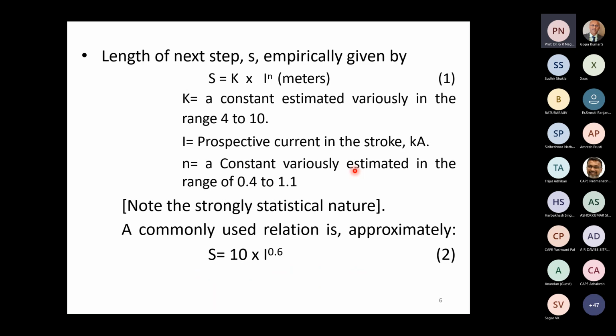Now, supposing the leader has come to the point P naught as shown in the previous figure, the length of the next step was shown to be related to the prospective current I in the stroke by the relationship given here. Yes, the next step distance is equal to a constant K multiplied by the current I raised to the power of N. Now, remember, lightning has many statistical parameters. That means we cannot have one constant for K. Similarly, we cannot have one constant for N. For strokes which have occurred in some area, for various currents in that region, we may find different values of K and N. Like that, the constant K, estimated variously globally, has a range of 4 to 10. It is a little surprising, is it not? Very surprising, 4 to 10, 1 to 2.5 times.